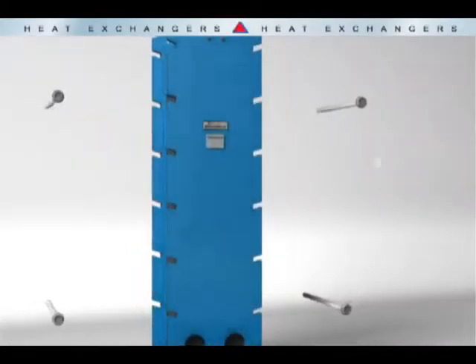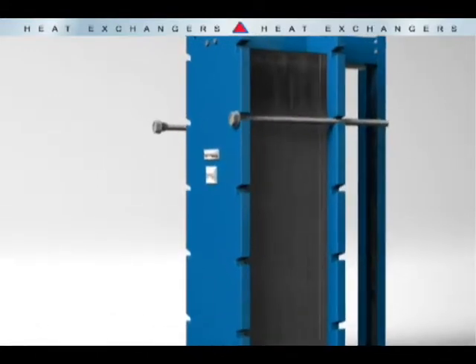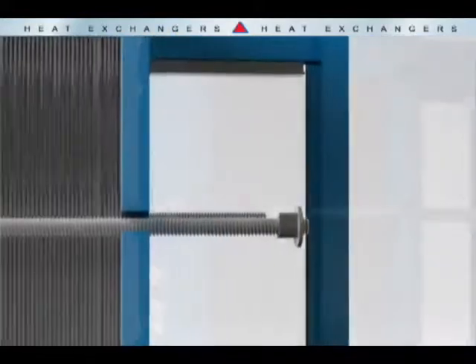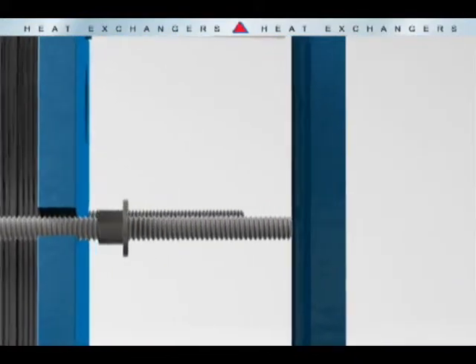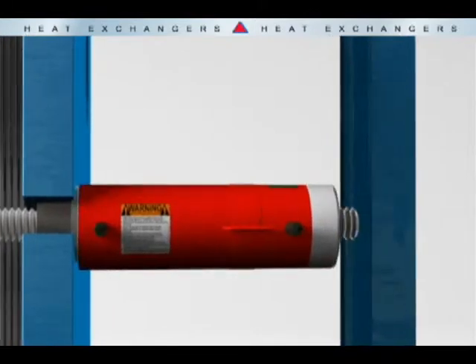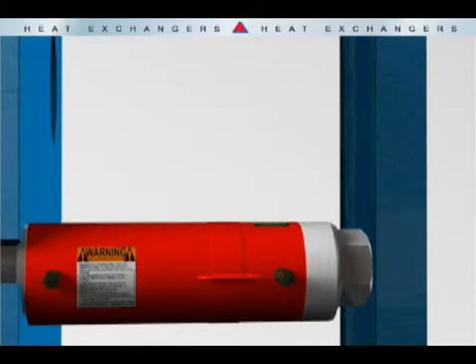Load the compression bolts with bolt guide inserts in the correct notches. Now install the Easy Changer cylinders. Secure them with washers and nuts snugged to the cylinder rod ends.